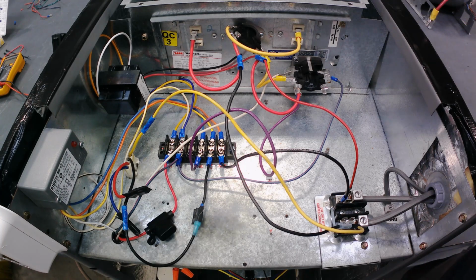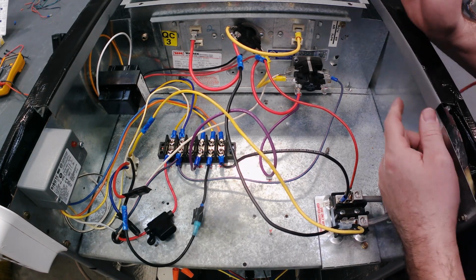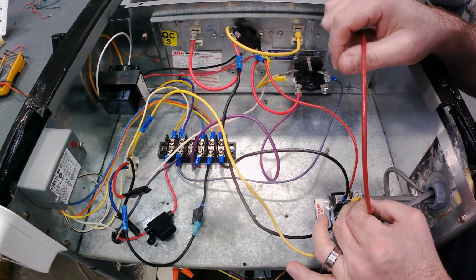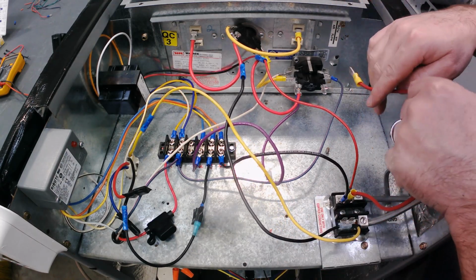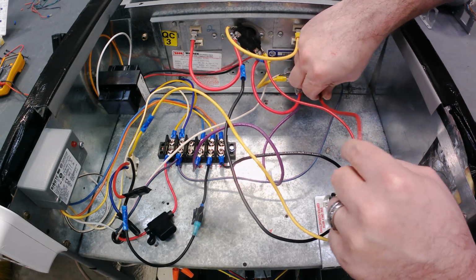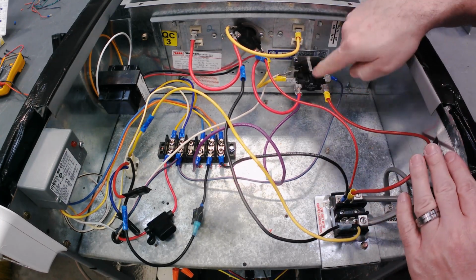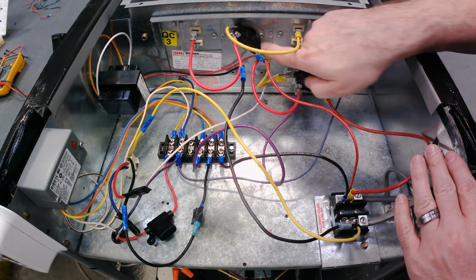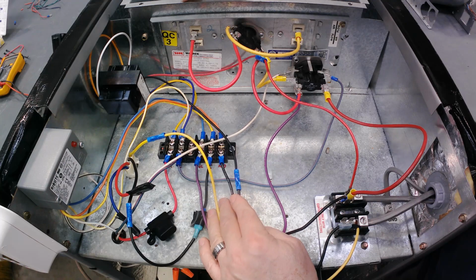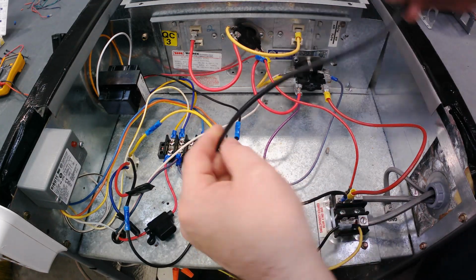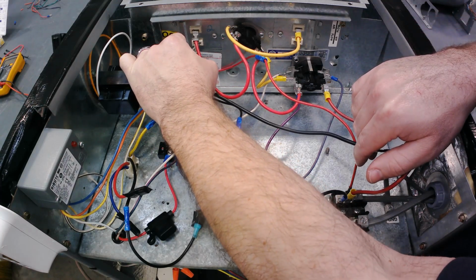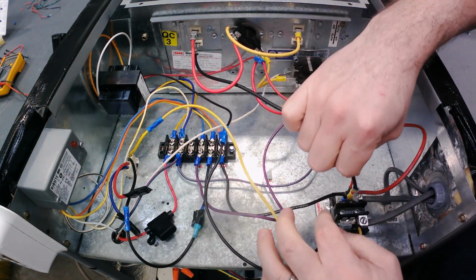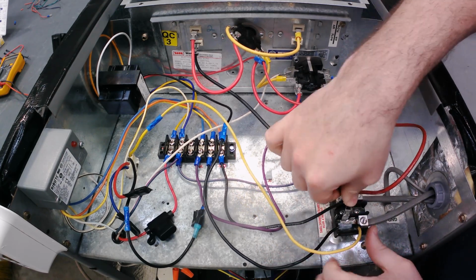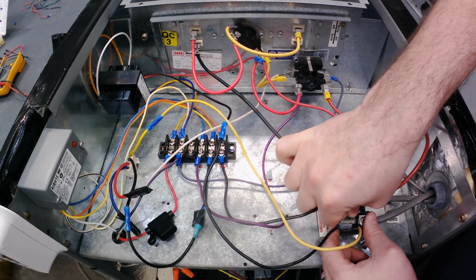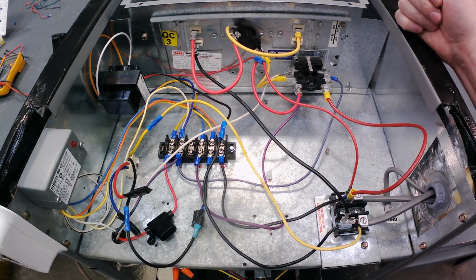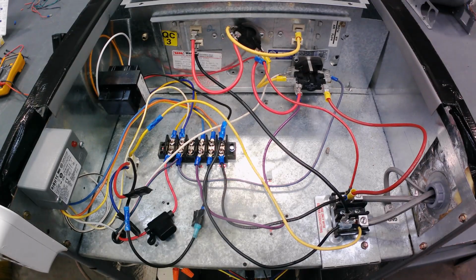And now we'll wire up our heat strip just to finish it out. So pretty much what I did, I'm going to take L1, and then I'm going to go power into the sequencer. And the sequencer, once it's closed, is going to go through our limit here. It's going to pass power into this left heater, and when it comes out, we're going to have another wire over here, and that's a stretch, actually. Yep, that's a stretch, but it gets the point. So we're going to do some voltage checks and be done.